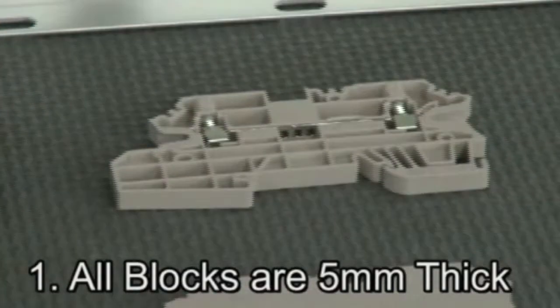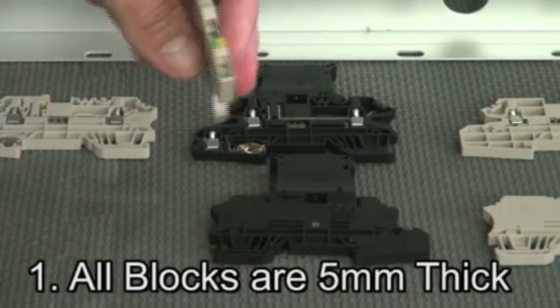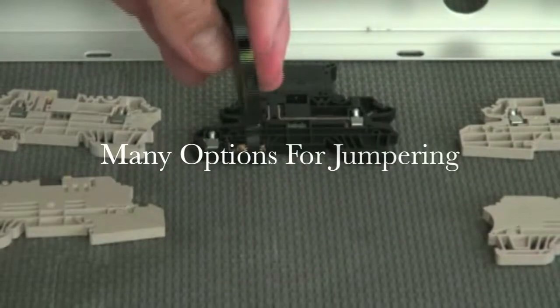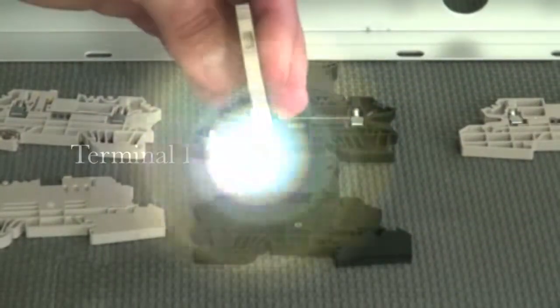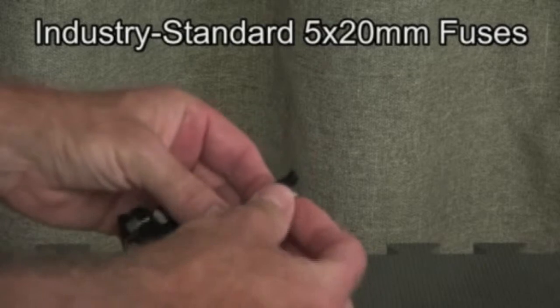All of the blocks in this series are 5 millimeters thick. This consistent block thickness provides many options for your cross-connection or jumpering requirements and makes terminal block marking a breeze. This 5 millimeter effective thickness is possible because the fuse holder is located above the body of the terminal block. These fuse blocks accept industry standard 5 by 20 millimeter fuses.